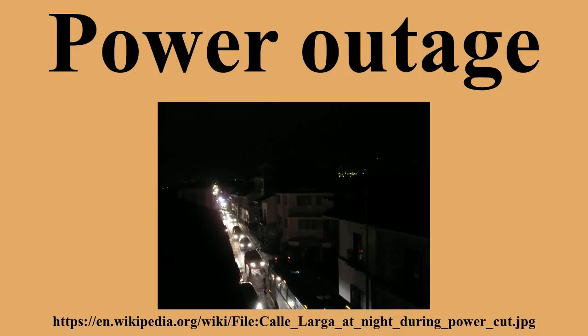Power failures are particularly critical at sites where the environment and public safety are at risk. Institutions such as hospitals, sewage treatment plants, mines, and the like will usually have backup power sources such as standby generators, which will automatically start up when electrical power is lost. Other critical systems, such as telecommunication, are also required to have emergency power. The battery room of a telephone exchange usually has arrays of lead-acid batteries for backup and also a socket for connecting a generator during extended periods of outage.